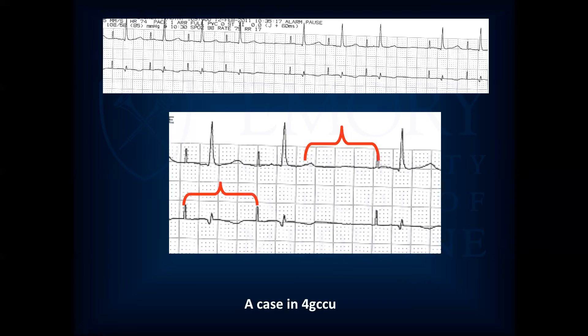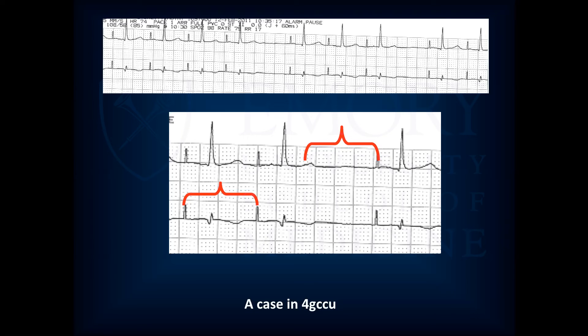A question about the previous example: how is this different from the Medtronic MVP feature? The MVP allows for atrial events without ventricular — so you'd see an A event with no conduction. That's the distinction: with T-wave oversensing there's no intrinsic atrial event, whereas MVP shows an atrial event without ventricular conduction.